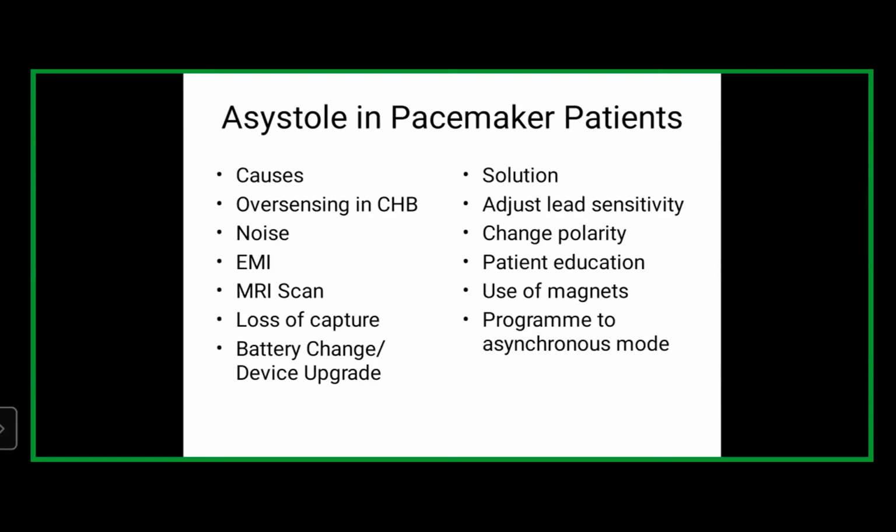And if the lead was programmed too sensitive, you can adjust the sensitivity so that it will not sense noise or some background, perhaps even myopotentials, or whatever the source of noise might be, and think it's intrinsic electrical activity of the heart, and withhold pacing.